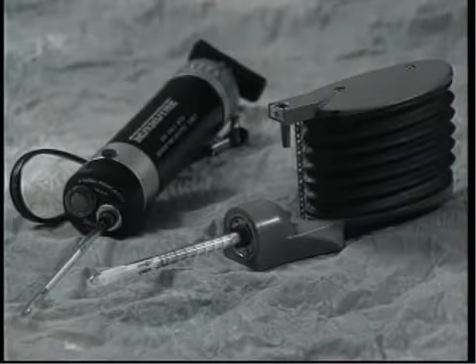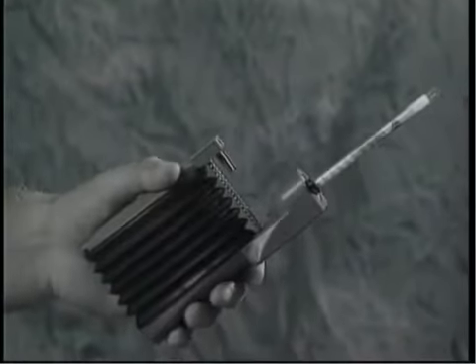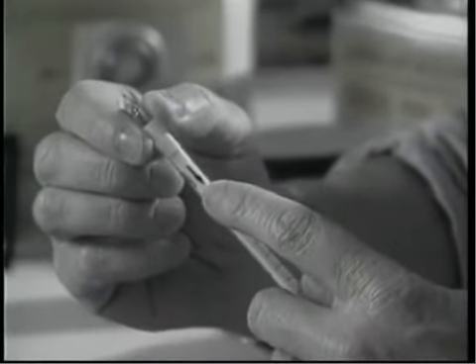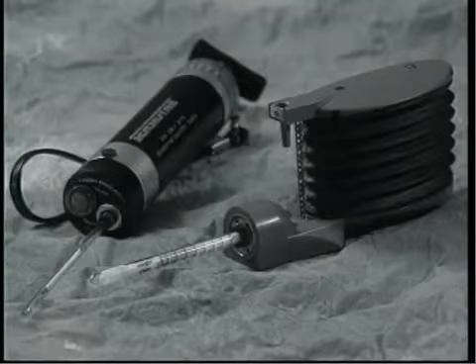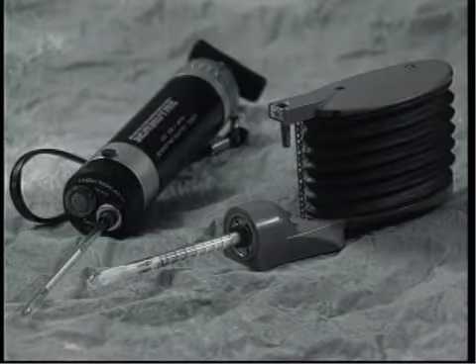The second method consists of using tubes that change color to indicate the gas concentration. These tubes are used with a special pump that draws a sample of air through the tubes. The further the color goes along the tube, the higher the gas concentration. Different kinds of tubes are used to indicate different gas concentrations, so each type of gas requires a different tube. Low-level detecting tubes for concentrations from 0.15 to 5 parts per million are suitable for most uses.